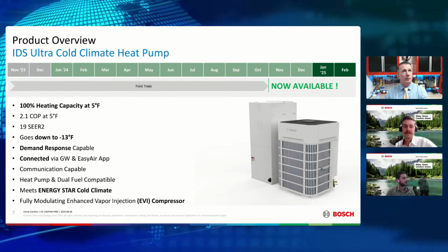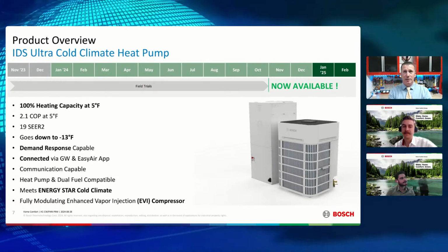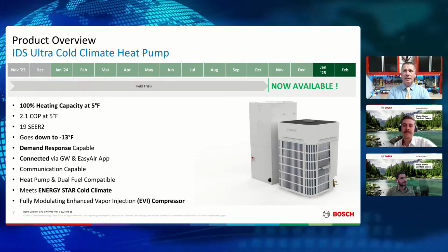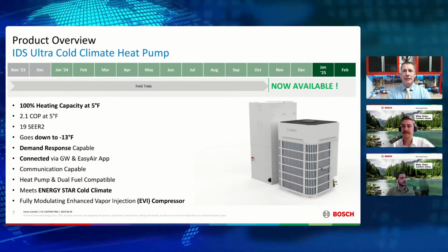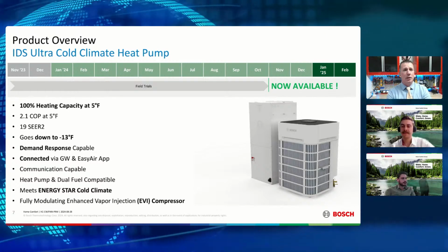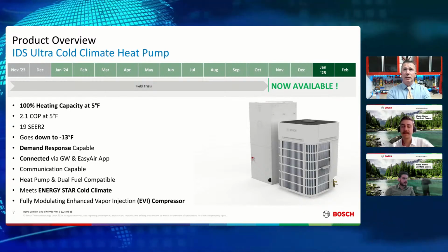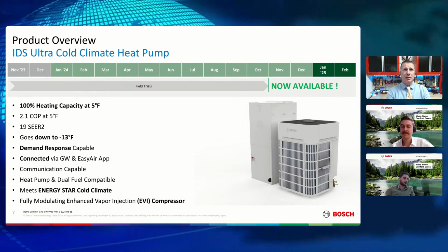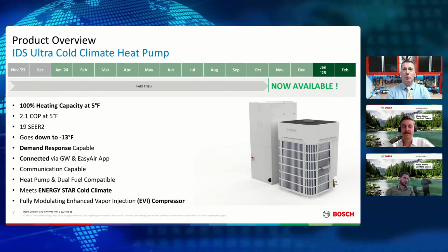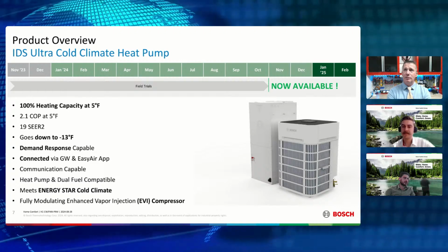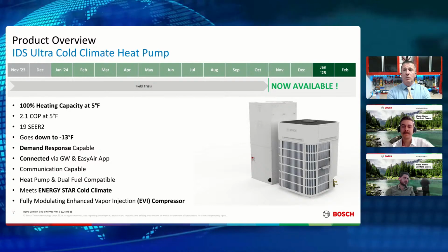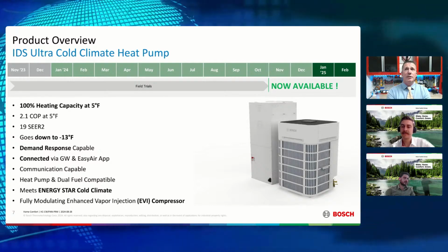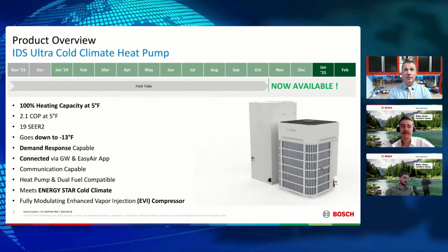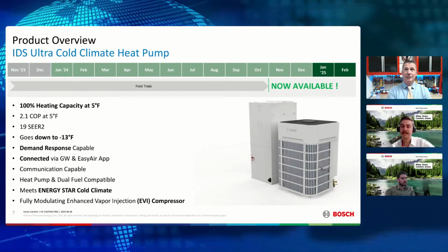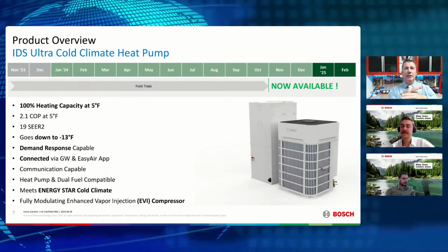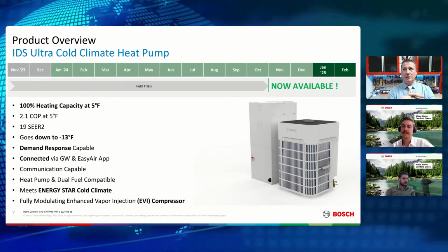Sure. So when we start talking about capabilities of heat pumps, remember there was a time when we looked at balance points of a system completely based on our heat gain, heat loss. Now we actually start re-looking at our balance point from an efficiency perspective. Because if we look at this particular unit at 5 degrees, I'm still putting out 100% capacity. And I'm doing that at a COP of 2.1. So 210% efficient, approximately, compared to electric resistive heating alone at 5 degrees. And so, what we previously looked at as a BTU balance point is really starting to get challenged now by efficiency, because with this particular unit, I would look at that at 5 degrees and go, okay, I've still got enough capacity. Let's just keep on running until I get down to a mix of my heat gain, heat loss balance point and my energy efficiency balance point.